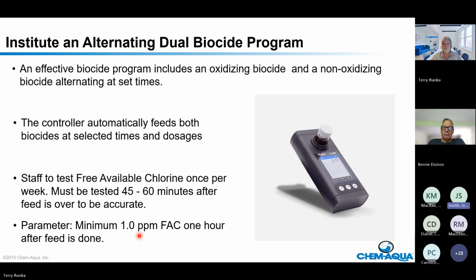We test our free and total chlorine levels on the days that we pump, and we are consistently getting about 0.5, and it doesn't seem to matter how much chlorine we're pumping in. Right now we're running it for 50 minutes and it's not going up very much. Oddly enough, on our second smaller tower, we're actually getting a high chlorine reading on the off days, but not on the on days.